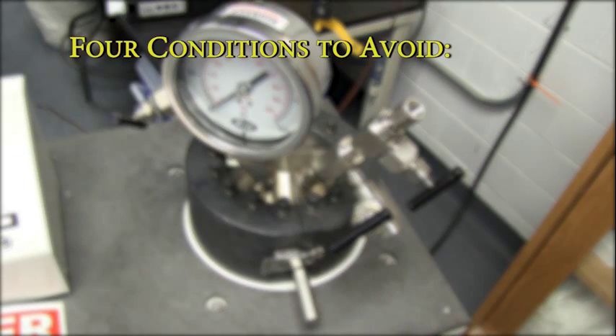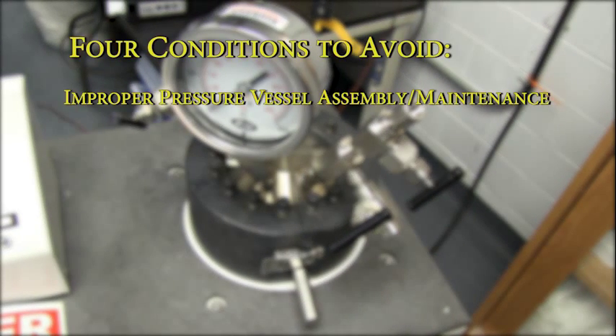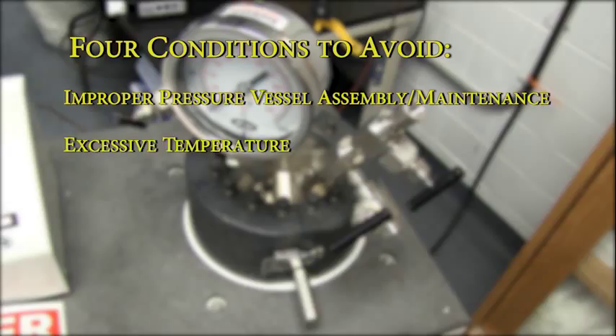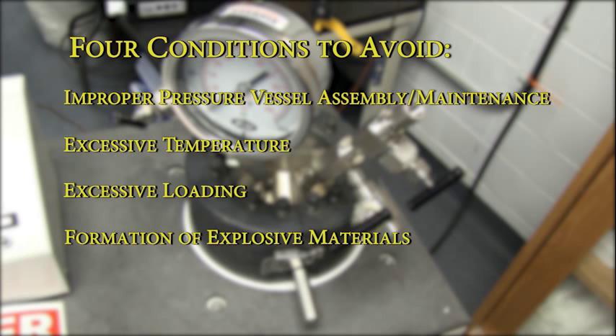Four conditions you want to avoid are improper pressure vessel assembly or maintenance, excessive temperature, excessive loading, and the formation of explosive materials.